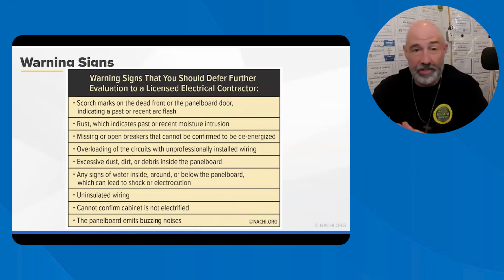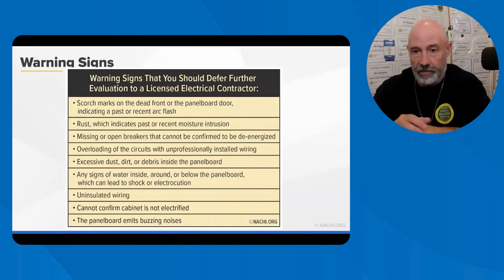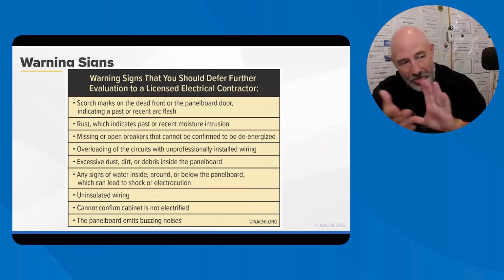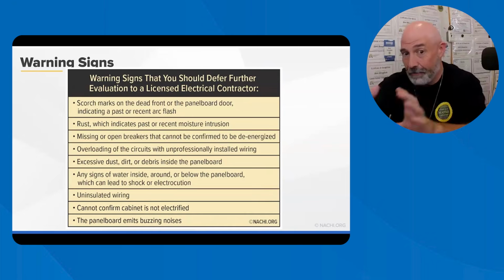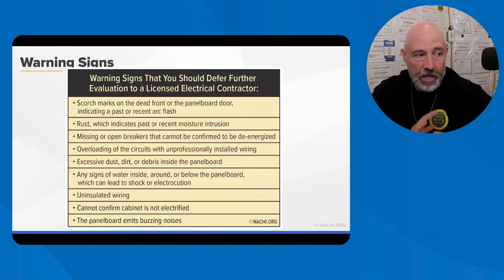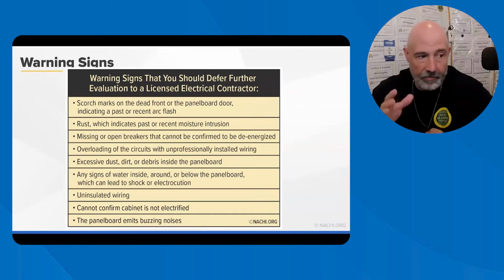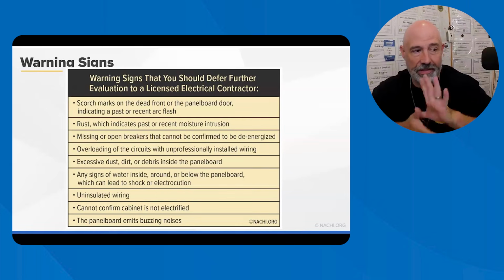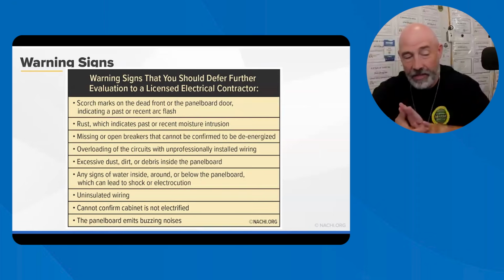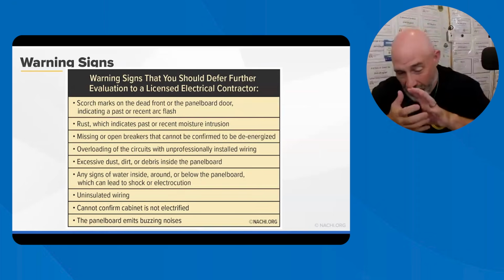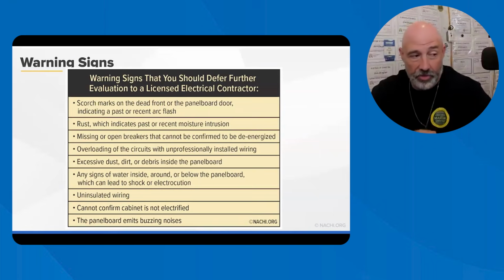Overcurrent circuits, a lot of times I'll see that on an air conditioner. It'll say 25 amp max, and then there's a 50 amp circuit breaker for that, and that's not good. You should actually have 25 amps max. So I call that out quite a bit. Any signs of water inside the panel, you don't really want to even open that up if that's the case. Uninsulated wires, you see that quite a bit, and you can't call out everything because sometimes you can't see it, but try to make sure that you call out as much as you possibly can when it comes to electrical safety.